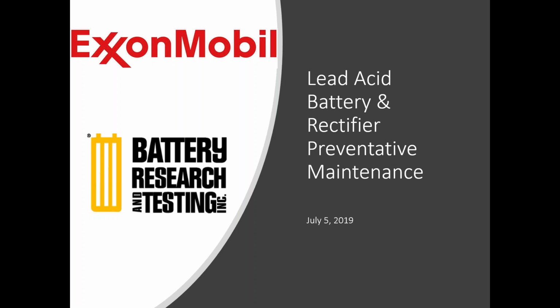Right now, the way I see equalization being utilized is really if you came off a deep discharge or batteries were stored for an extended period of time, it can help drive sulfates off the positive plates. Any kind of sulfation or crystallization that you may have, it can help in that end. It also obviously speeds up getting the battery back in quicker. But even there, you really don't want to do it because of the heat and everything that comes with pumping a lot of current back into a discharged battery.